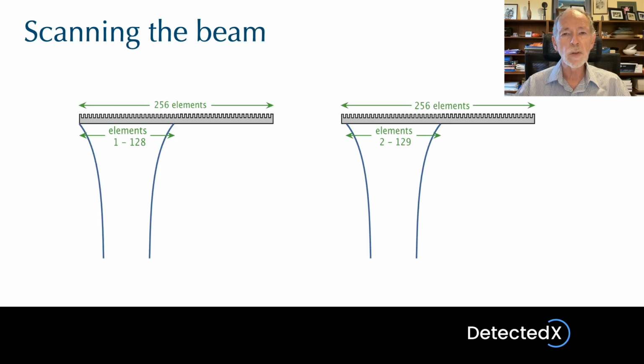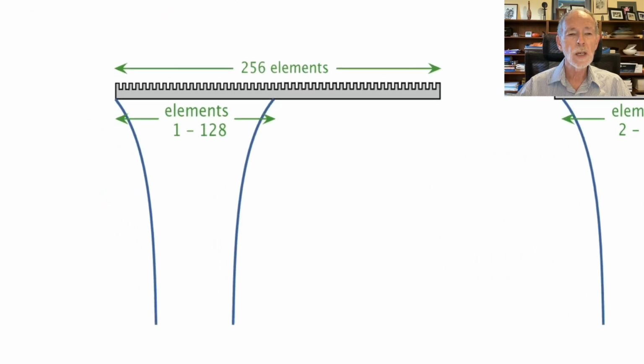So here we have a side view of the transducer, and you can see it cut up into its elements. I've just as an example said, let us suppose there are 256 elements. That's a binary number. It's not just a number plucked out of the air. And let's suppose 1/2 of the elements, 128, are used at any one time to form the beam. The first beam would be formed using elements 1, 2, 3, 4, up to element number 128. And that would form a focused beam. The machine would transmit down that beam, receive echoes along that beam, and then when it had received all the echoes that were detectable, the beam would be shifted slightly to the right and the process repeated.